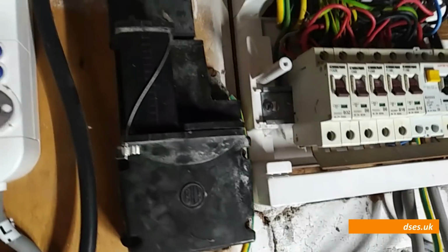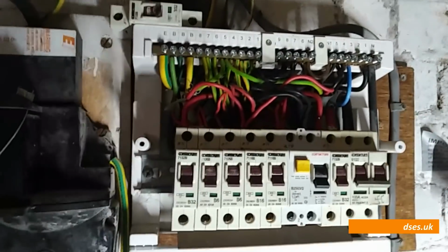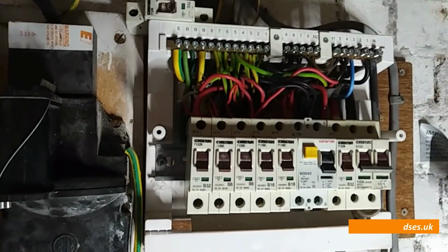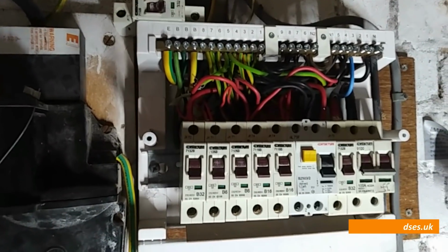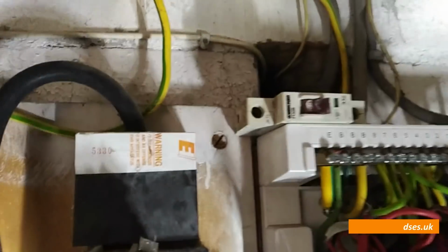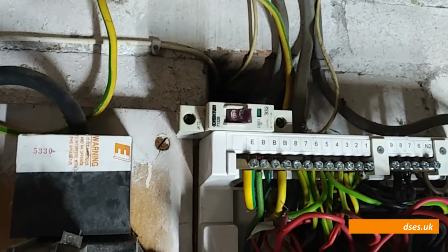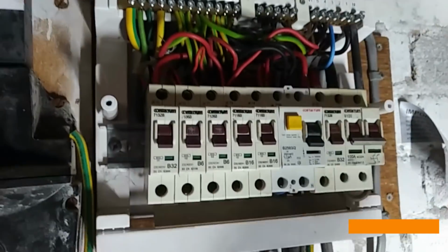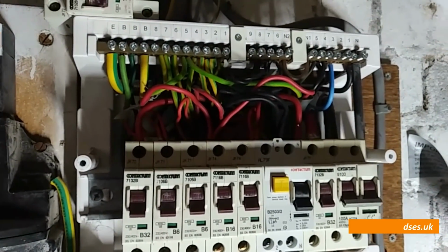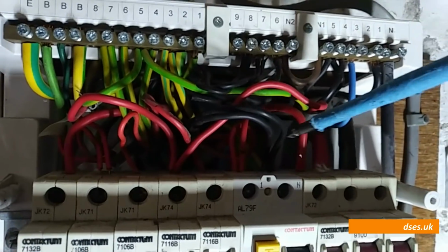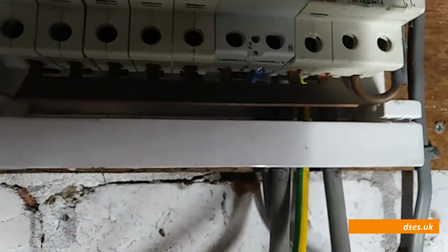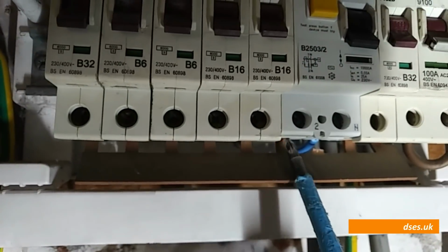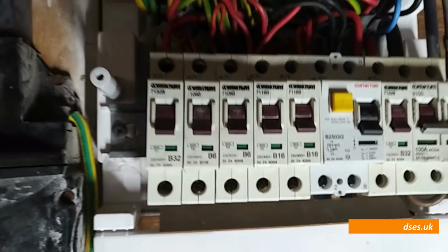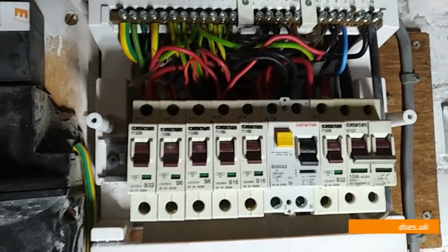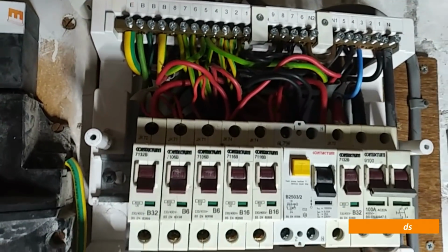Someone has done an EICR here, I think about 10 years or so ago according to the label, which I won't show you on the board. But it's interesting because if you notice, what we have sitting up here is a 32 amp MCB sitting doing nothing, and what we have here is this device providing additional protection for the socket circuit. We can see there that we've got the line and neutral going in at the top, and at the bottom we have the busbar going into the live side. The busbar has been cut here to allow the neutral connection of this two-pole device to be made to the neutral bar, which is the only bit that's in newer colours by the looks of it.